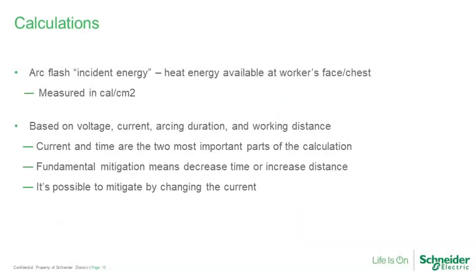So, some key takeaways from the calculations. Arc flash incident energy is something we'll talk about in several places through this presentation. What we're looking at is the heat energy available at a worker's face and chest, measured in calories per centimeter squared. That's the typical unit that clothing is rated in, and the typical unit the calculations are performed in as well. Arc flash incident energy levels are based on four primary parameters. First, the voltage and current available in the system, and with current, we mean the short circuit current at the given piece of equipment you're looking at.